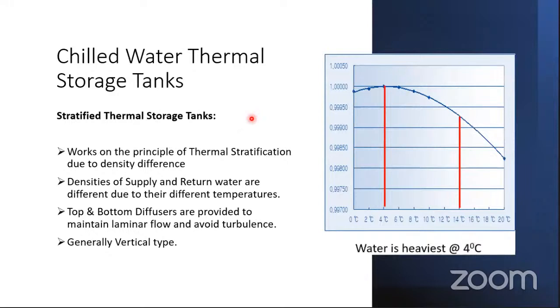So chill water thermal storage tank. This is the first category that we are trying to understand here, the stratified thermal storage tank, in which the working principle is that it works on thermal stratification because of the density difference. Like in the same tank that is vertical, like I've written here, it's a vertical tank in which when the chill water is discharged and the return water is coming back from the top, the idea is that mixing should be controlled. No turbulent mixing should happen between the two. And for that, the densities of supply and return water are different due to the different temperatures. So it's the density difference that causes the thermal stratification to happen naturally.